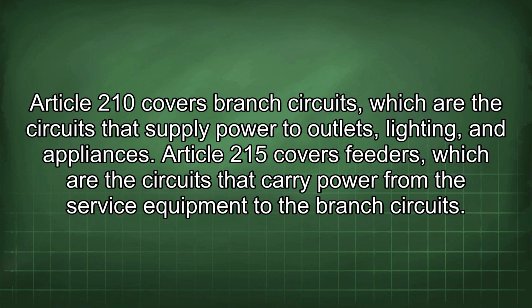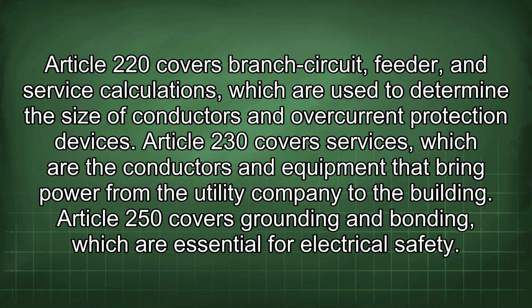Article 210 covers branch circuits, which are the circuits that supply power to outlets, lighting, and appliances. Article 215 covers feeders, which are the circuits that carry power from the service equipment to the branch circuits. Article 220 covers branch circuit, feeder, and service calculations, which are used to determine the size of conductors and overcurrent protection devices. Article 230 covers services, which are the conductors and equipment that bring power from the utility company to the building. Article 250 covers grounding and bonding, which are essential for electrical safety.